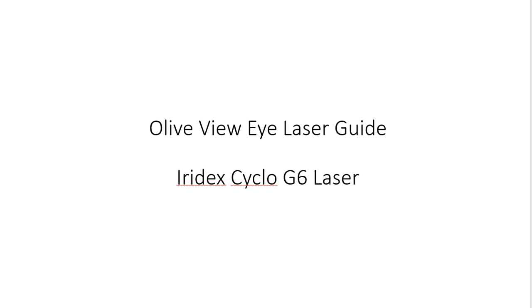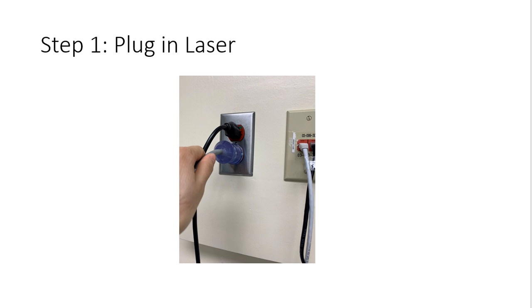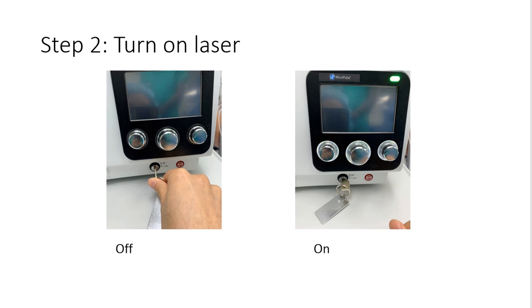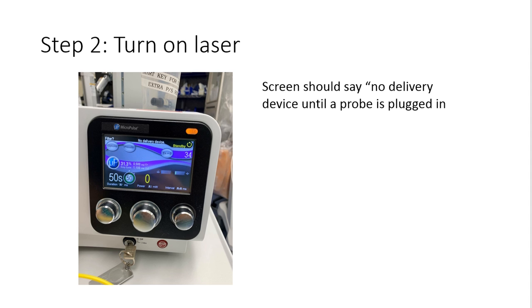This is a guide for using the Iridex Cyclo G6 laser in the operating room. First step is to plug in the laser. After that, turn the laser on. Here the key is shown in the off and on positions. When you turn on the laser, the screen is going to say no delivery device until a probe is plugged in.